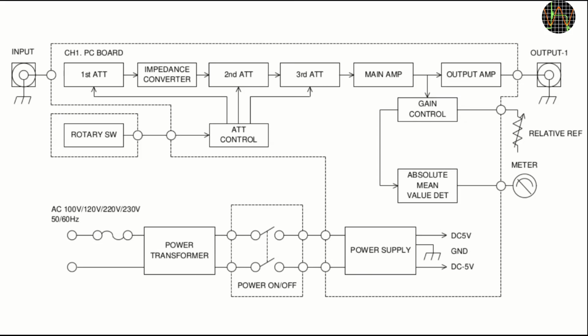First, the block diagram. Note that this says CH1, presumably channel 1, implying that there is a dual channel version. The circuit is quite straightforward. The input signal goes through an impedance converter and 3 attenuator stages to the main amplifier. From there it branches. One path goes to the meter, which shows the rectified mean value. The relative knob allows adjusting the amount of signal going to the instrument. The other branch goes to a second amplifier, which provides the output signal.